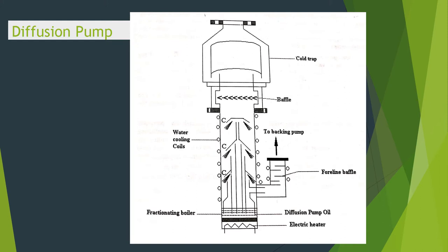Looking at the figure of a diffusion pump, you can see a boiler containing the diffusion pump oil. The bottom part is closed with an electric heater. When heat is applied, the vapor produced moves upward through annular jets. This portion is known as the chimney. The baffle valve and water cooling coils are placed here to condense the vapors.